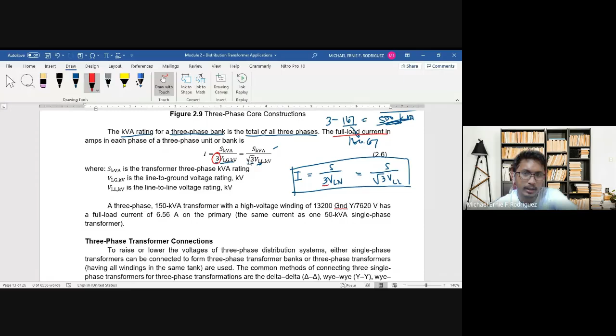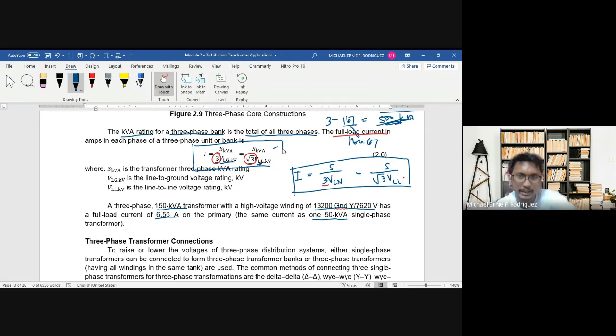Okay, if anyone is confused, remember: 3 for line to ground, square root of 3 for line to line. So we have a 150 kVA transformer, same high voltage winding, giving 6.56 amperes on the primary, same as a single 50 kVA transformer, since what we used is the line-to value. So this is the same current as a 50 kVA single phase transformer. That's our formula, take note of it, it also comes from your circuits course.